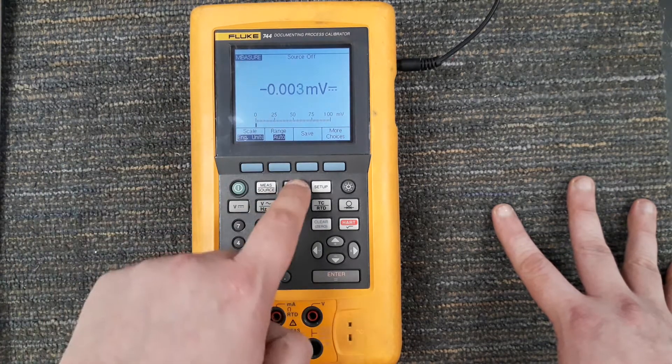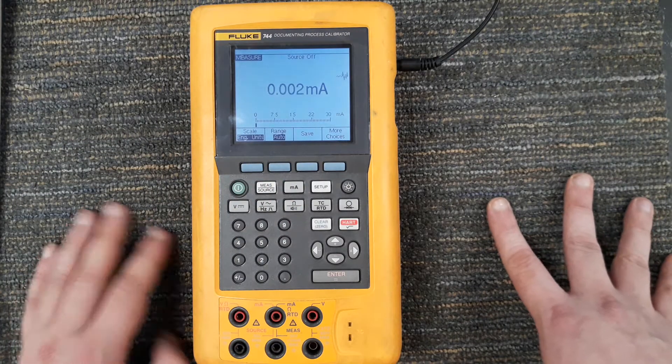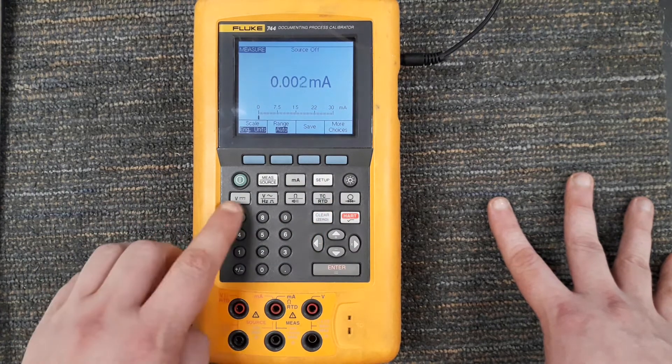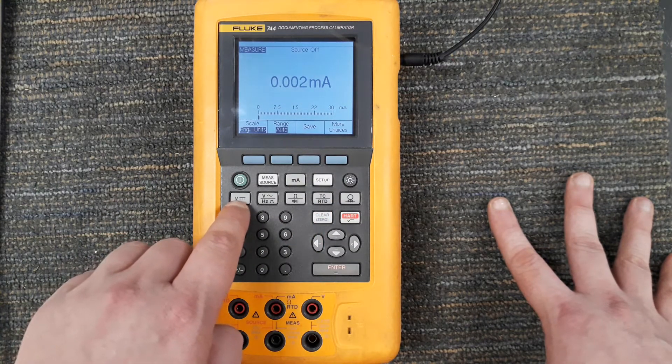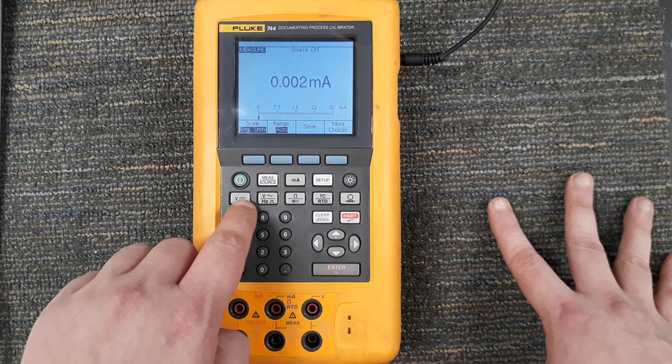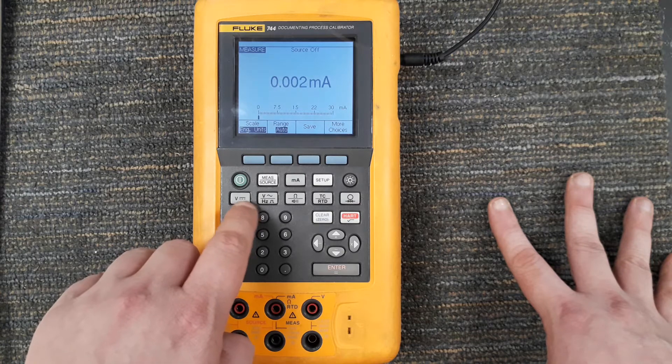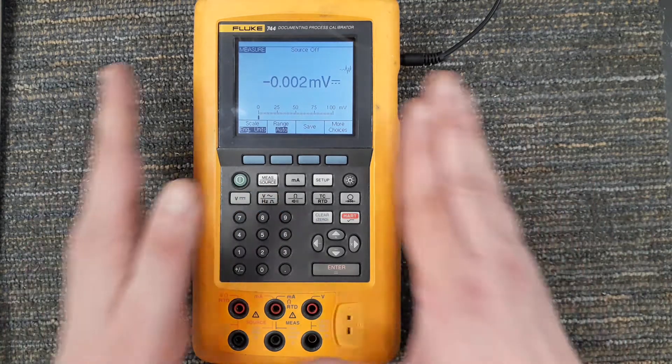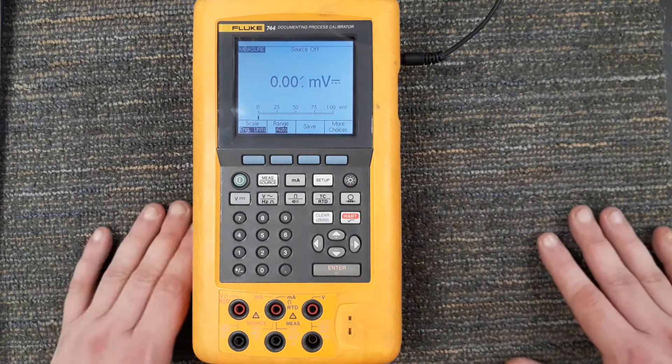I'll be covering how we use all that in separate videos for measuring source. This one should look familiar - milliamps. It's going to have to line up in conjunction with whether I'm measuring or sourcing. I'll hit the milliamp button - we can source current. Volts DC - if you look at the V for volts and you remember the symbol for your standard Fluke symbols for DC voltage, you have solid line with the dash line. I can source DC voltage. I can source AC voltage. Now I'm not going to source AC voltage that's going to power an appliance with this thing.